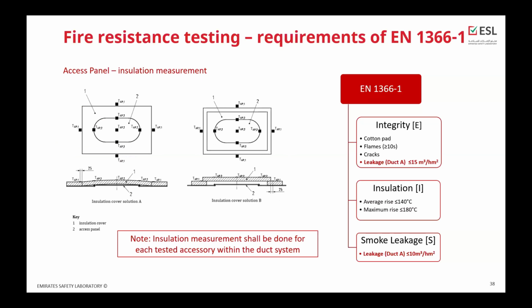The European standard also provides details on how to assess the accessories. For example, here you can see the access panel and the placement of the thermocouples to assess insulation of access panels. You also need to remember that insulation measurements shall be done on each accessory which is part of the duct system: access panel, VCD damper, sound attenuator, or compensator.